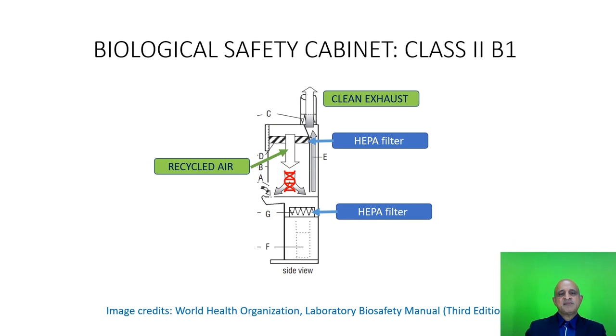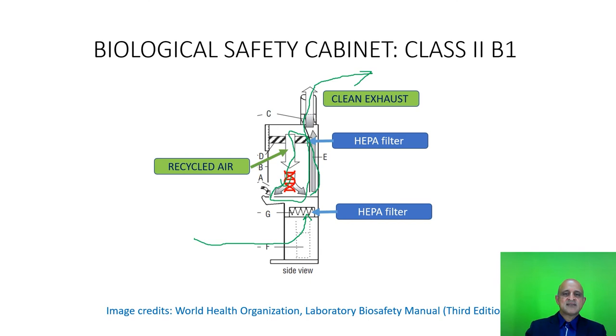This is a schematic diagram representing the biological safety cabinet. Air enters via a HEPA filter, is circulated over the biological agent, flows out, and then passes into the environment via a HEPA filter. It is a cyclical process and air is then exhausted out. The operator who stands in front of the cabinet is protected from the biological agent by virtue of directional airflow.